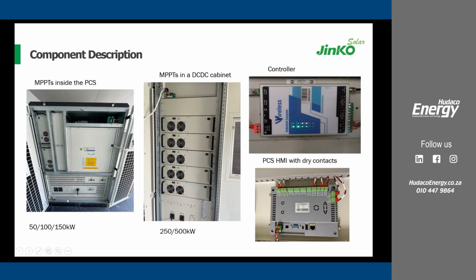This is basically included. Then we have the DC-DC modules. You can see we have 50 kilowatts and 50 kilowatts to make 100 kilowatts, which we can still expand to 200 kilowatts. We can still add two modules, so 50 kilowatts by 4 makes 200 kilowatts. Then on the PCS, of course, with all the auxiliary breakers, you can see this for the 250. This is the standalone DC-DC cabinet.